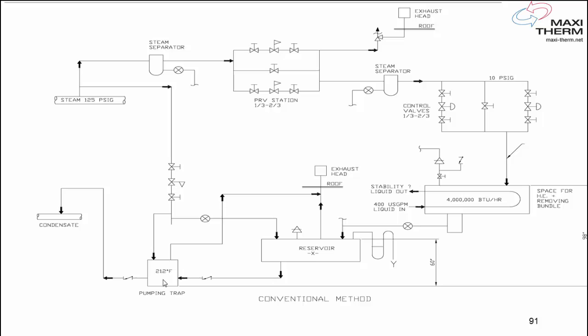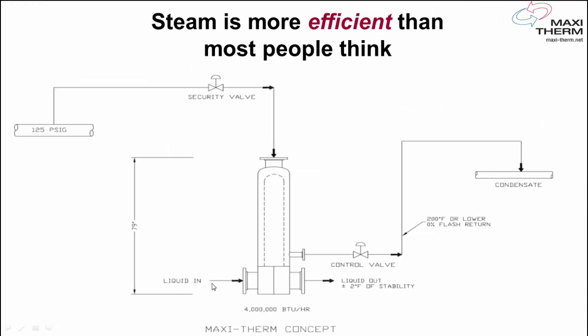So what if you no longer needed any of these? No more pressure-reducing valve, no more safety valve, no more 1/3–2/3 big control valve, no more flash tank, and no more condensate pump. Well, that's exactly what Maxi-Therm does. We use a vertical flooded heat exchanger. We put the control valve on the condensate — a very small one, 1/2 inch size — and that's it. Because we are more efficient at high pressure by flooding the heat exchanger, we extract more heat from each pound of steam.